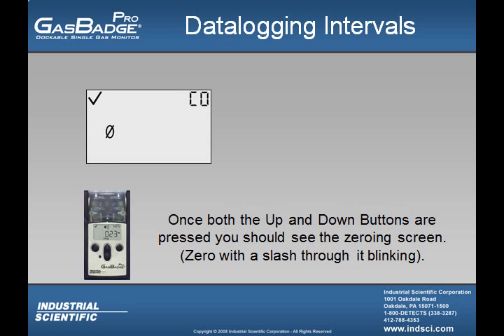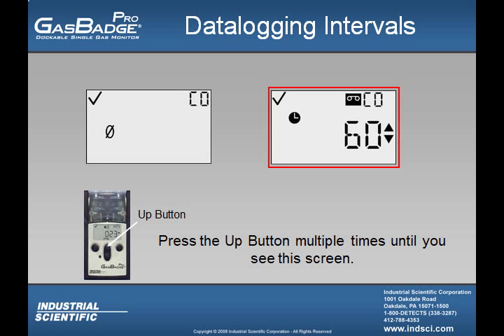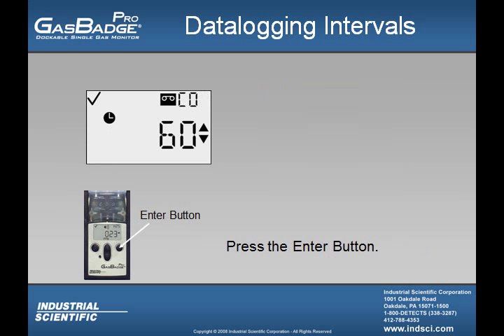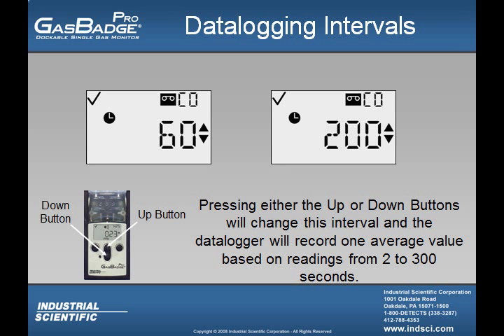As soon as the user is in the configuration menu, the first thing they should see is the zero with a slash icon blinking. The user must press the up button multiple times until they see the cassette tape icon just like the one shown on the right. After the user sees this icon, they must press the enter button. Once they press the enter button, they will see the numbers start to flash. The user can then press the up or down buttons to change this value anywhere from 2 to 300 seconds. This value reflects the amount of time the Gas Badge Pro will accumulate the average exposure data before writing it to the data logger.